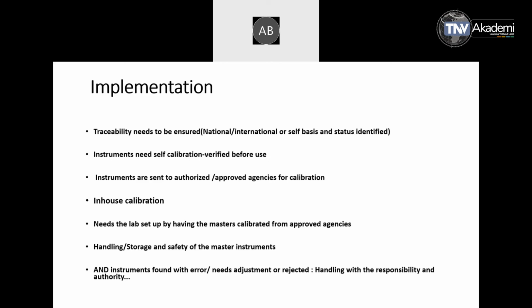The errors will not be what we are noting, because while handling itself, error has been created in the master instruments. There are instruments which are very sophisticated. If they are not stored at the correct temperature, humidity and safe conditions on soft beds, they may start giving errors. So the handling, storage and safety of the master instrument is very important.